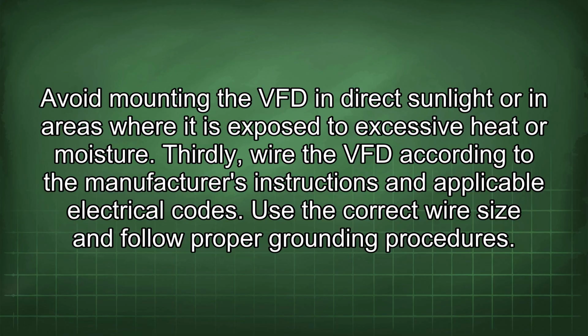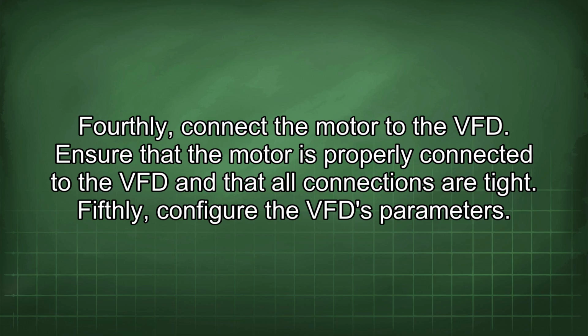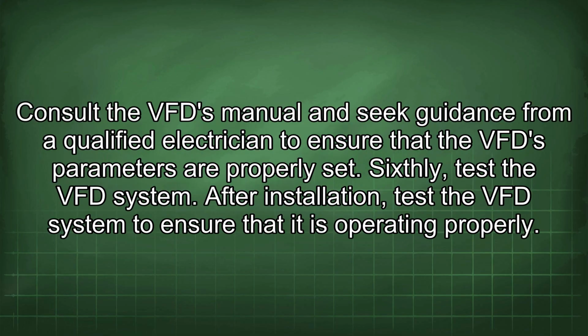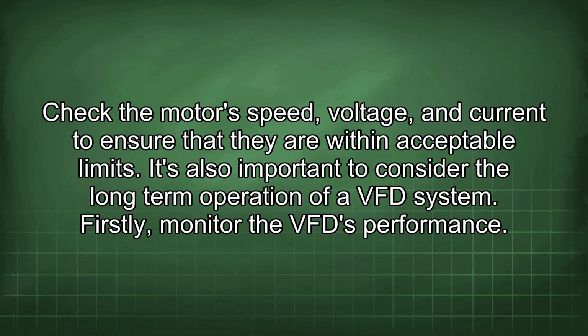Thirdly, wire the VFD according to the manufacturer's instructions and applicable electrical codes. Use the correct wire size and follow proper grounding procedures. Fourthly, connect the motor to the VFD. Ensure that the motor is properly connected to the VFD and that all connections are tight. Fifthly, configure the VFD parameters. Consult the VFD manual and seek guidance from a qualified electrician to ensure that the VFD parameters are properly set. Sixthly, test the VFD system. After installation, test the VFD system to ensure that it is operating properly. Check the motor's speed, voltage, and current to ensure that they are within acceptable limits.